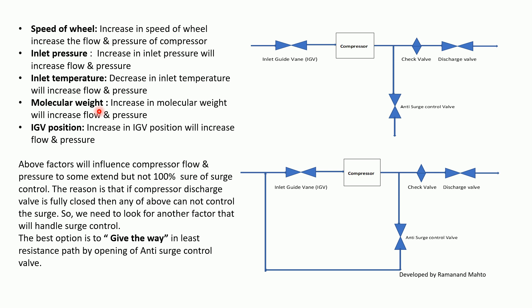If the density of the gas increases, the pressure and flow through the compressor will increase. However, these factors will influence compressor flow and pressure only to some extent, and are not 100% reliable for surge control.